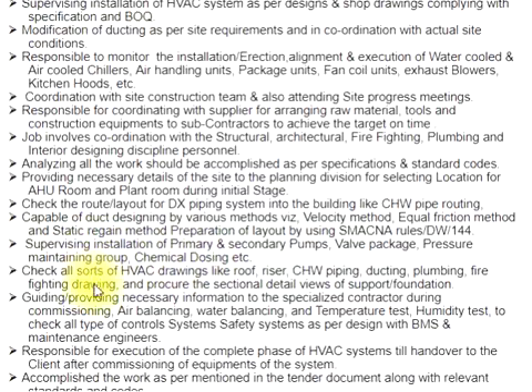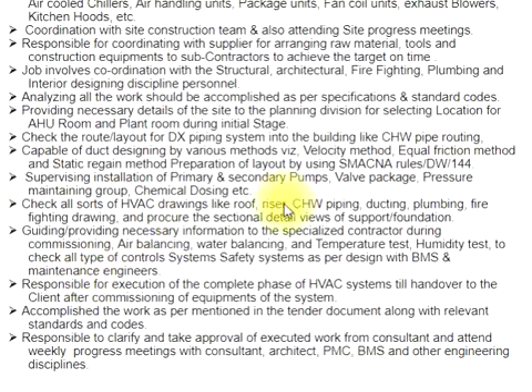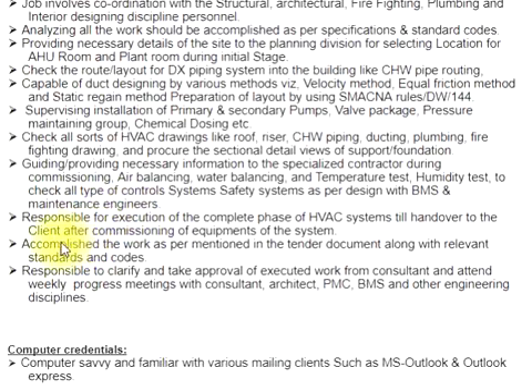Check all sorts of HVAC drawings like roof, riser, CHW piping, ducting, plumbing, firefighting drawing, and procure the sectional detail views of support, foundation, guiding, providing necessary information to the specialized contractor during commissioning, air balancing, water balancing, and temperature test, humidity test. To check all types of control systems and safety systems as per design with BMS and maintenance engineers.